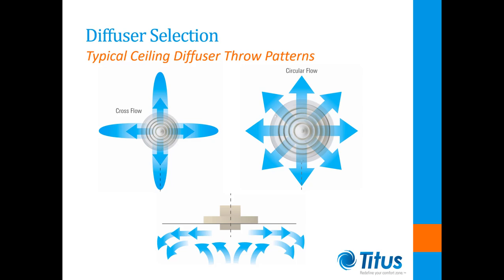With high performance hoods that have a capture velocity around 50 feet per minute, this means keeping any air motion in front of a hood to 25 feet per minute or less, which can be extremely challenging to maintain. In addition to occupants, another source of potential disturbance is air motion that results from diffusers in the lab. Typical ceiling diffusers are designed to have extended and high velocity throw patterns that create a well-mixed space, but could result in air streams traveling down the face of the hood and should not be used.